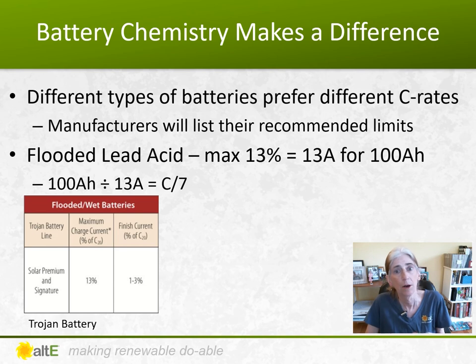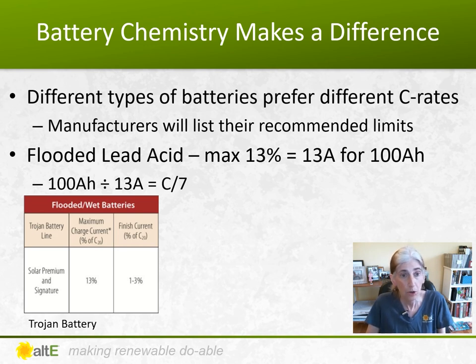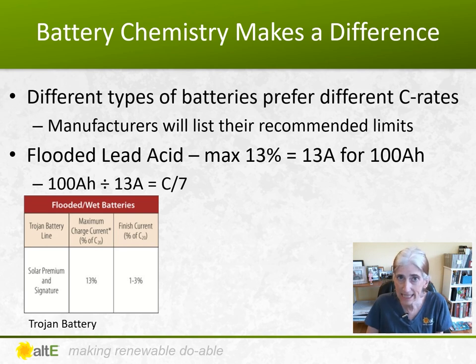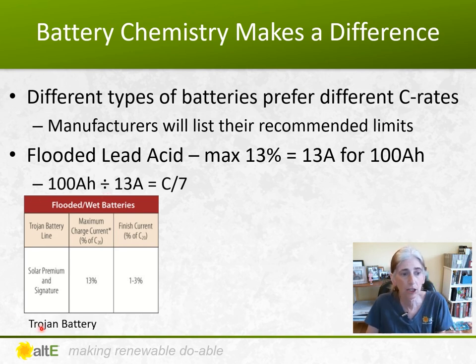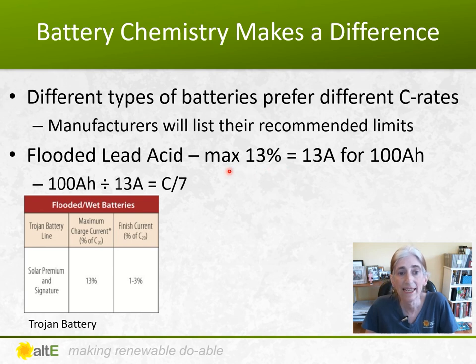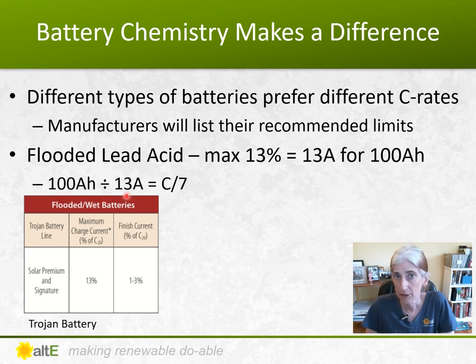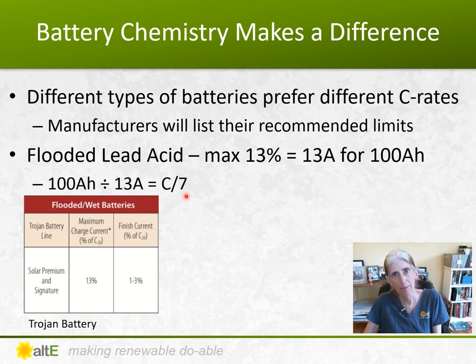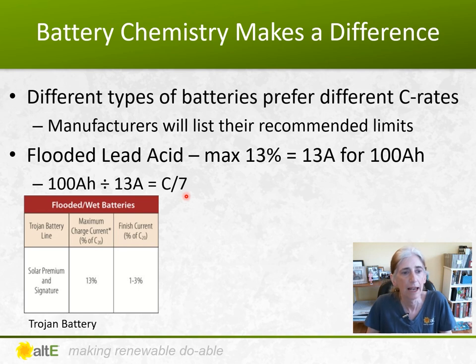Different types of batteries prefer different C rates, and manufacturers will list their recommended limits. Looking at a Trojan flooded lead acid battery as an example, its maximum recommended charge rate is 13%. So for a 100 amp hour battery, that's 13 amps, giving a C7 rate. That's their recommended ideal charge rate — not too fast, not too slow. It makes for a happy battery.